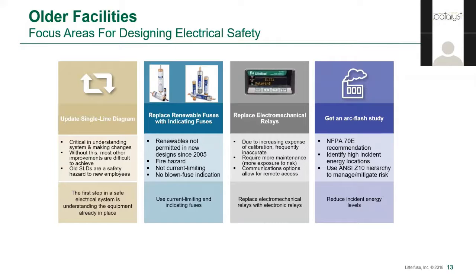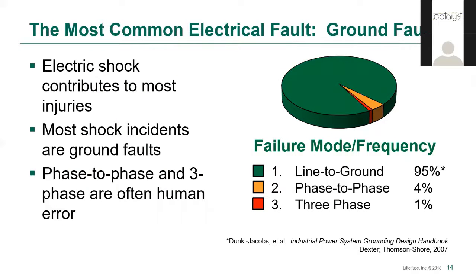Hopefully most of you have done an arc flash study by now, but if not, it's definitely recommended to help identify high-risk areas. The results of the study can be used as a start to managing that risk, including the hierarchy of controls we just spoke of. When we talk about updated single-line diagrams being important, one key piece is the grounding system. Most electrical faults — 95% of them — are ground faults. The majority of electrical injuries are shock-related, and most shocks are ground faults. They often escalate from ground faults; only about 5% of electrical faults are not initiated by ground faults, and in these cases the root cause is usually miswiring, accidental shorting, or human error.